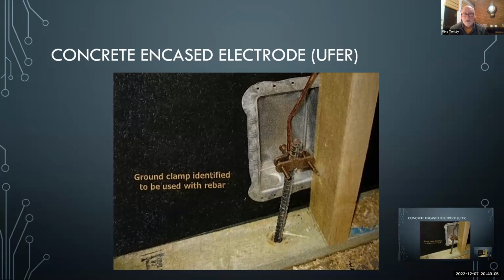Well, let me back up on that. If one is present, like an underground water pipe, it has to be tied to the system. It's not the sole electrode, but it has to be included and bonded to the grounding electrode system. We'll talk more about that in a minute. But that's a UFER, and they generally bring them up like this in garages, crawl spaces, wherever they're accessible. They have to be accessible.